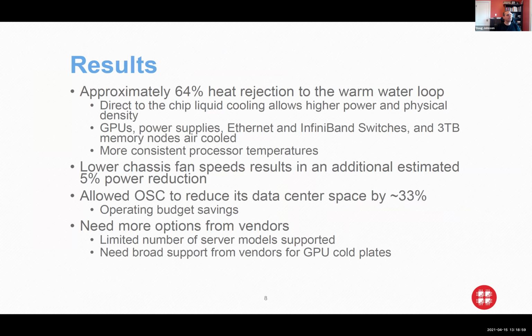So what are our results? After the upgrade, when we brought in the Pitzer expansion and a slightly more efficient CDU, a newer version of the coolant distribution unit, we've seen an increase in the percentage of heat rejection to the warm water loop for the cluster. Approximately 64% of the heat dissipated from the cluster goes into the warm water loop.